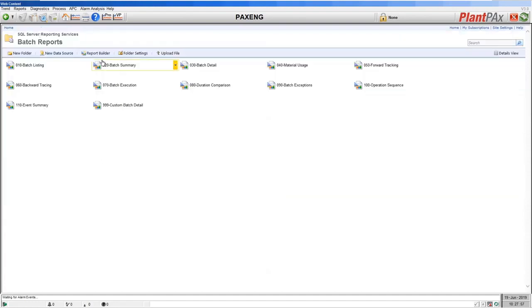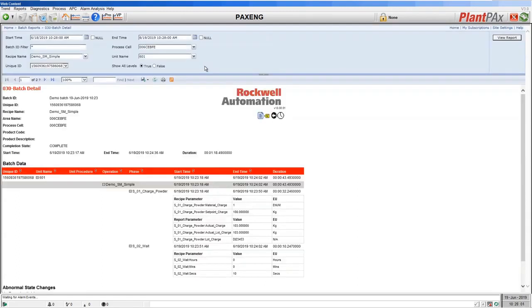Let's look at the next report: the batch detail. This has the same header information as the batch summary but gives more detail for each equipment phase as it ran. Here you can see for each phase the values of the parameters specified by Sequence Manager when they ran each equipment phase, and the report values those equipment phases logged back to the system.